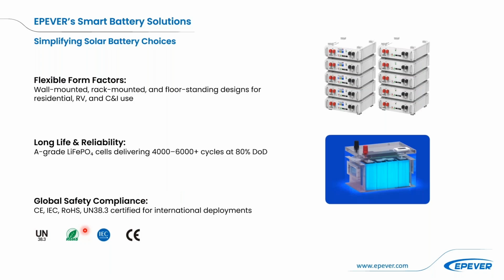Our long life and reliability promise comes from using A-grade LiFePO4 cells, delivering 4,000 to 6,000 life cycles at 80% depth of discharge. This directly counters rapid cycling wear and deep over-discharge damage, and by maintaining a comfortable working depth, we slow down chemical breakdown.